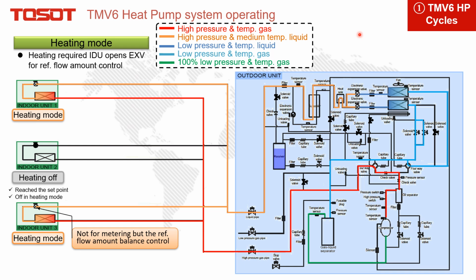If the outdoor temperature is low, then we need to apply the EVI, right? The purpose of it is just to increase the heating performance and also the capacity. How it operates is there is a subcooler here. A partial refrigerant will get through this EXV and get metered. Then it becomes low temperature, and then it can absorb heat, which makes it become gas. Then we inject this gas into the compressor to improve the performance.